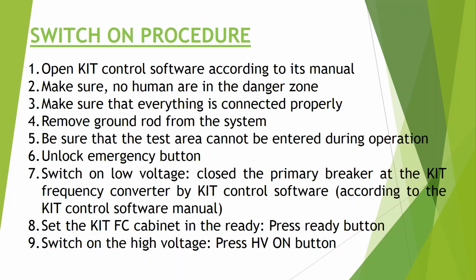Close the primary breaker at the Kit frequency converter by Kit control software, according to the Kit control software manual. Number 8. Set the Kit FC cabinet in the ready. Press ready button. And the last one is switch on the high voltage. Press HV on button. HV means high voltage. Okay, that settles the switch on procedure.